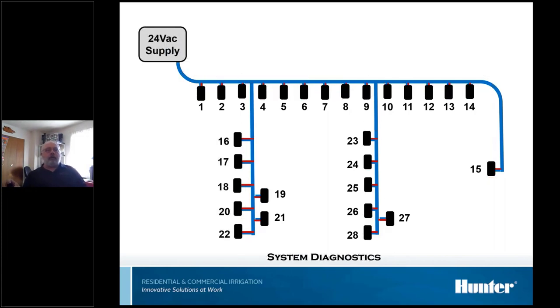So if we have a short, we hook up the power supply, and we might see numbers more like this. The check here, 2318. That's pretty high. That's high enough that I would actually put a solenoid in line. You wouldn't have to if you got a big transformer, but it's certainly high, and we should be able to find the problem this way. So now it's just a matter of going out and breaking it down. We call it the half method, basically. We go out to a T-splice and check it, and when we check this one, we read 47.